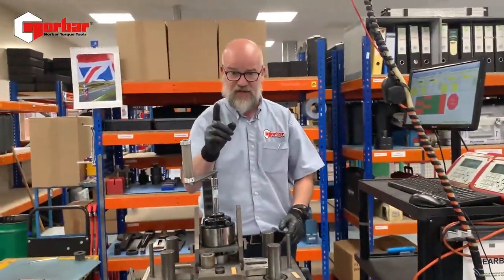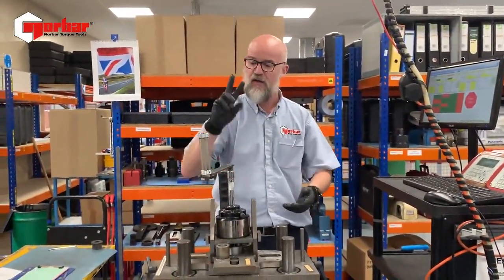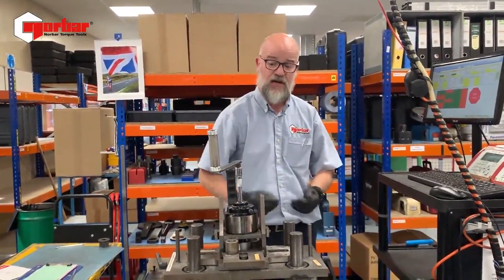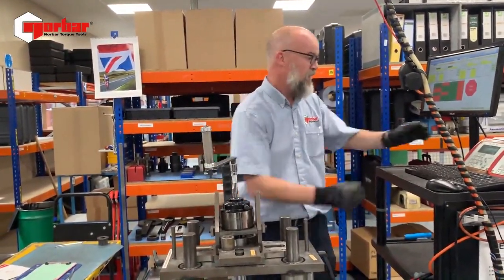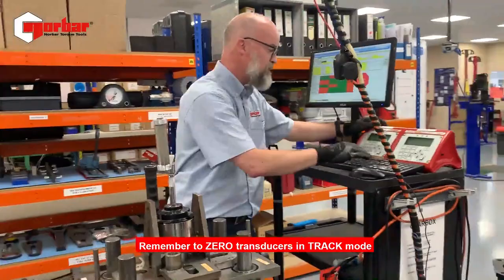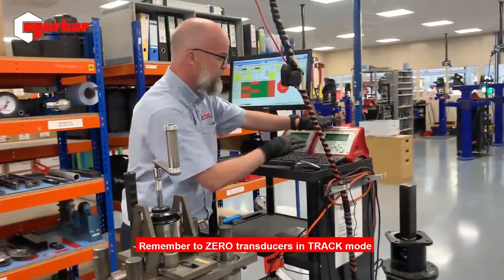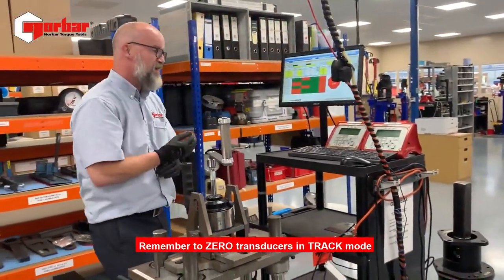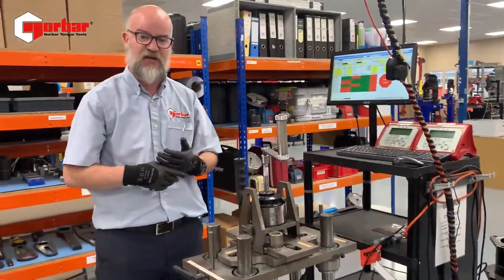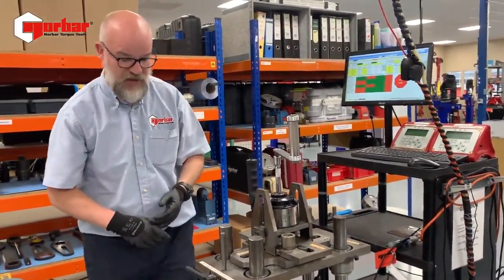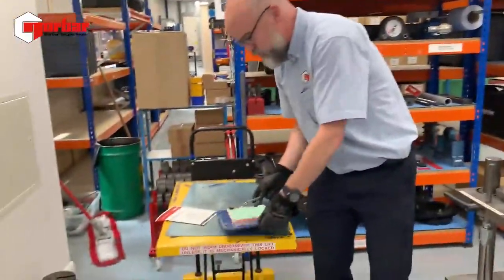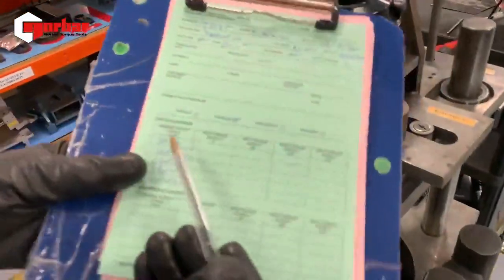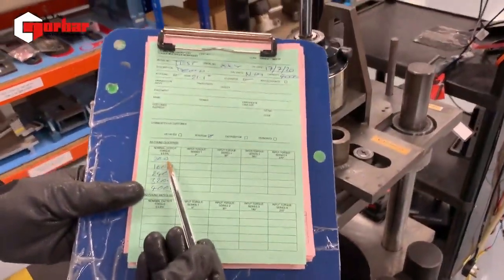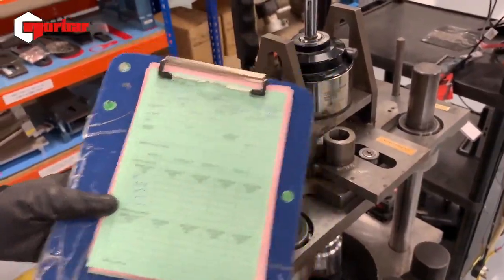What we can now do is load again, second time, load again, third time. Okay, we're going to release, and then we're going to zero. So we zero the input, zero the output, zero the input. So we're now in a position to actually start our calibration run. And again, to remind you, we're going to be working at 20% intervals. So our first nominal output torque is going to be 800 Newton meters.